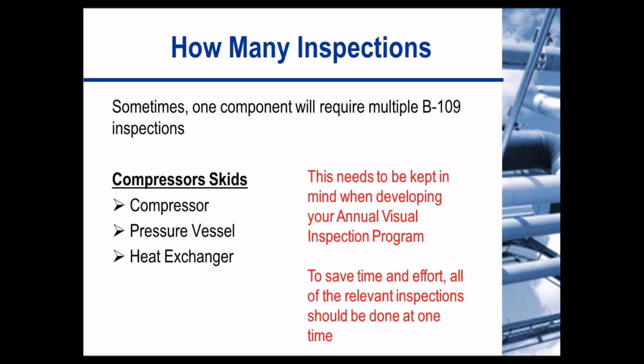Now, how many inspections? Sometimes one component will require multiple B109 inspections. This needs to be kept in mind when developing your annual inspection program. An example of this is the compressor skids. In the compressor skids, you have several different components, including the compressor, pressure vessels, and the heat exchanger. And if you keep these things in mind, you can handle all these issues at the same time.